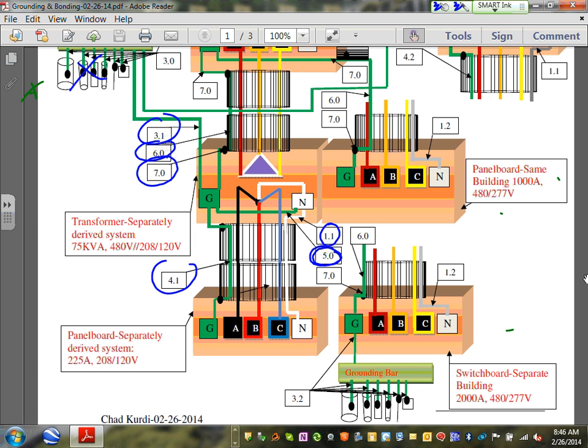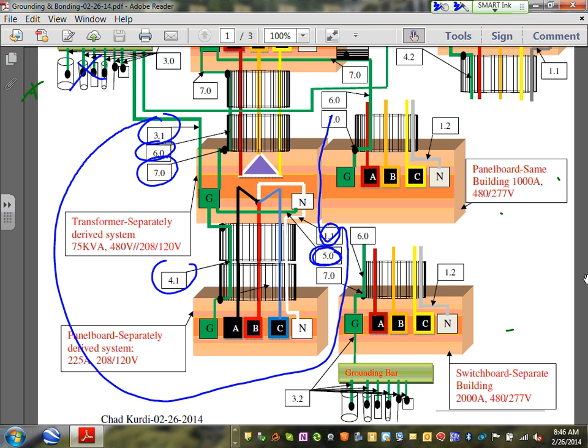And I want to remind you guys, my concern is right in here. I'm just concerned about this. I'm looking at this section. Any comments, guys, about the separately derived system? To summarize: a separately derived system is a transformer, delta primary, Y secondary, with complete isolation between the primary and the secondary conductors, the phases, and the neutral. When you have a transformer, you are to bond the new neutral that you created to the ground inside the transformer. Then you have to take a wire from the ground bar inside the transformer to the grounding electrode system up there.